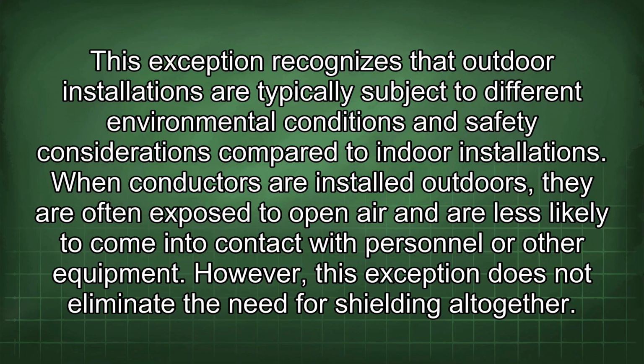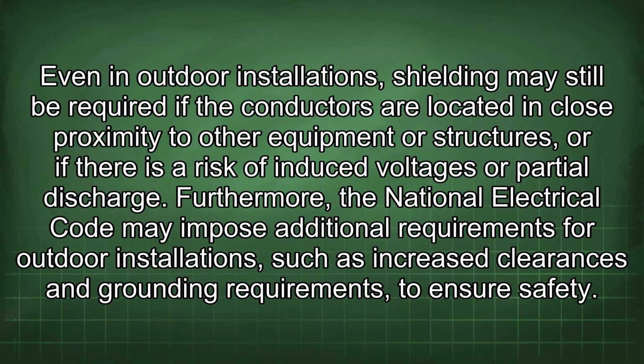This exception recognizes that outdoor installations are typically subject to different environmental conditions and safety considerations compared to indoor installations. When conductors are installed outdoors, they are often exposed to open air and are less likely to come into contact with personnel or other equipment. However, this exception does not eliminate the need for shielding altogether. Even in outdoor installations, shielding may still be required if the conductors are located in close proximity to other equipment or structures, or if there is a risk of induced voltages or partial discharge. Furthermore, the National Electrical Code may impose additional requirements for outdoor installations, such as increased clearances and grounding requirements to ensure safety.